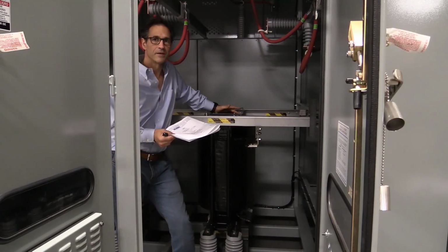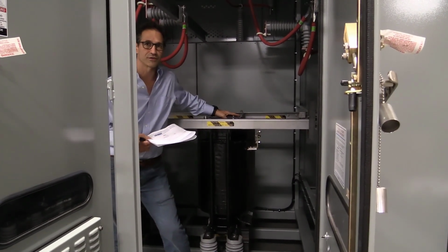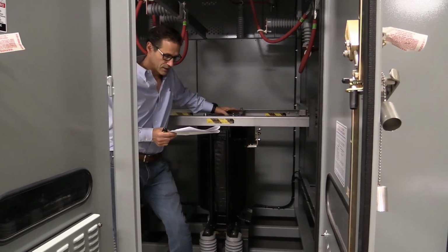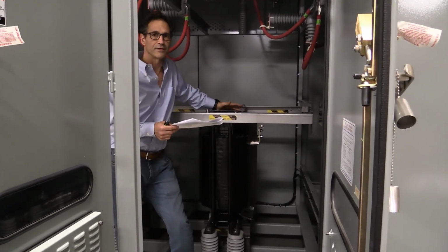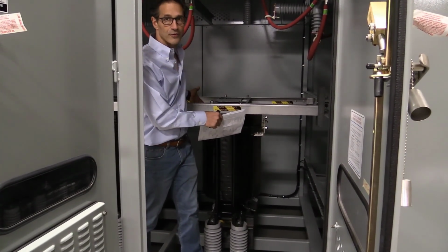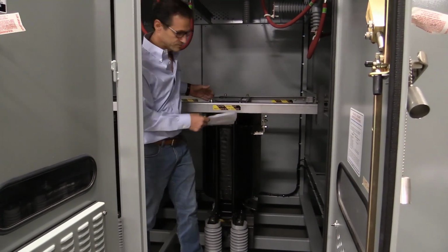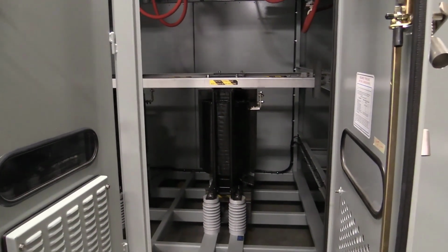The difference is the fundamental voltage drop across the reactor is much less in the higher tuned filter, and the harmonic frequency doesn't add to the flux density as quickly as a second tuned filter or third tuned filter. So as you go up in frequency, you can expect your iron core reactors to become smaller, even though they're at the same effective MVAR rating at the fundamental. All right, resistors.